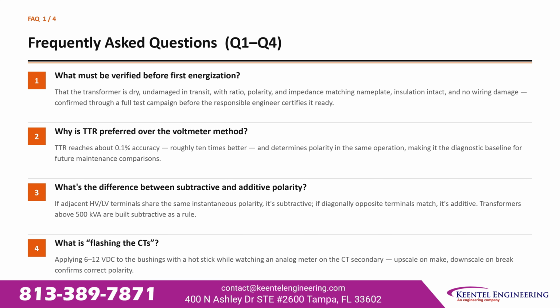What must be verified before first energization? That the transformer is dry, undamaged in transit, with ratio, polarity, and impedance matching nameplate, insulation intact, and no wiring damage, confirmed through a full test campaign before the responsible engineer certifies it ready.